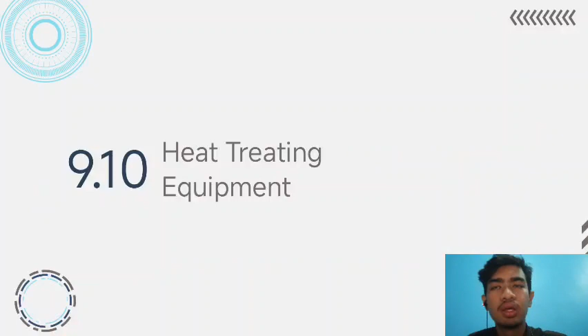And 9.10 is heat treating equipment. In simple terms, industrial heat treating furnaces are insulated enclosures designed to deliver heat to workloads. For thermal processing, basic elements of construction include an enclosure, refractory walls, a hearth or roof, a source of heat, and a means of accepting the workload, moving it through the furnace and removing it. Generally, furnaces are classified by heat source and by two broad categories, batch and continuous. Fuel-fired furnaces are most widely used, but electrically heated furnaces are used where they offer advantages that cannot always be measured in terms of fuel costs. Various types of batch and continuous furnaces are listed in the following. The batch furnaces are loaded with a charge, then closed for a pre-established heat cycle.